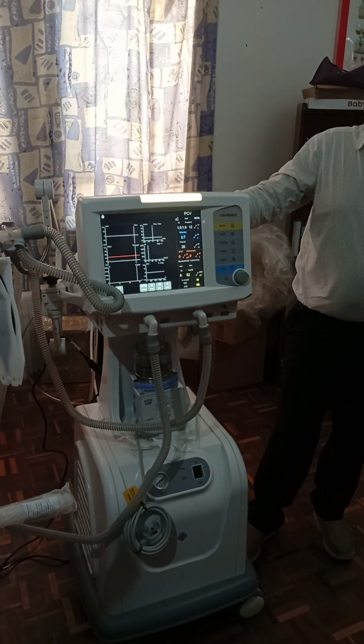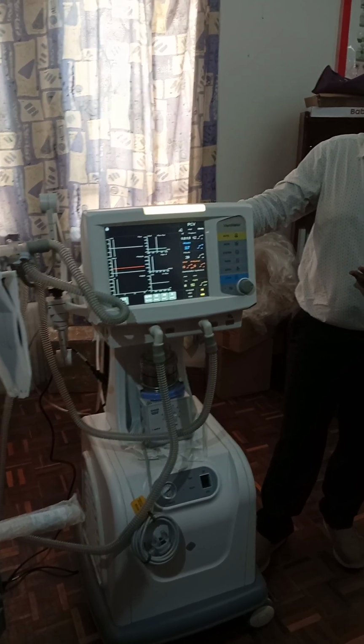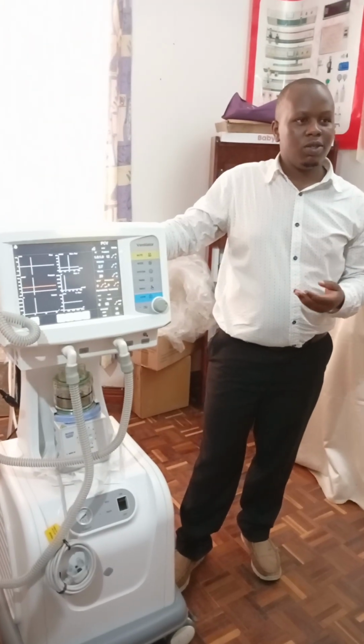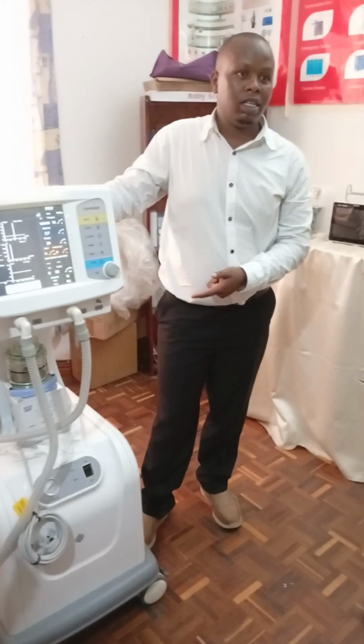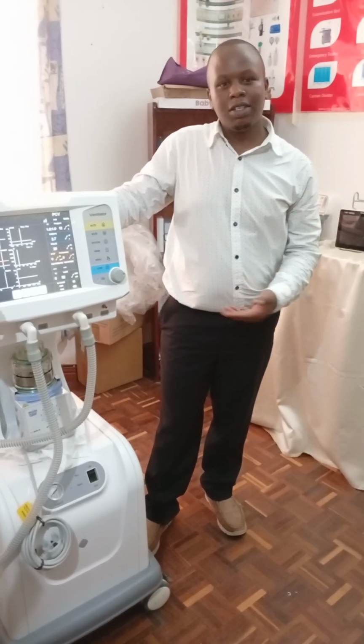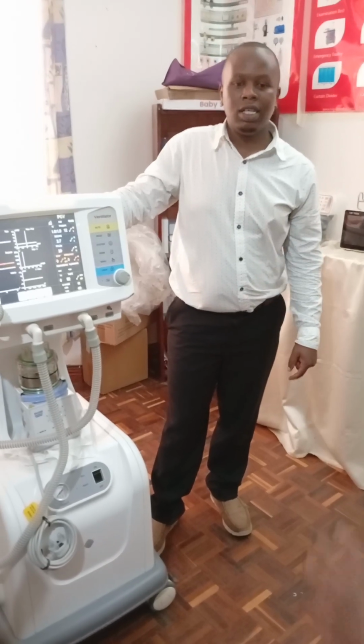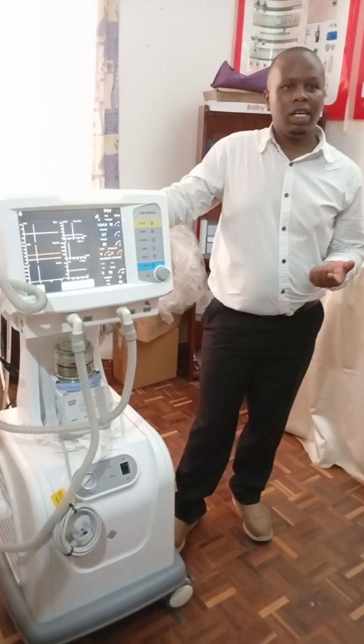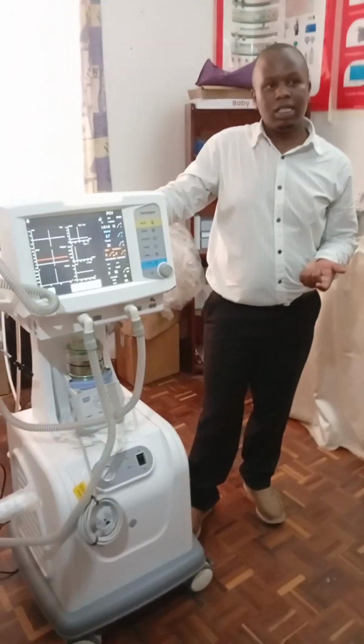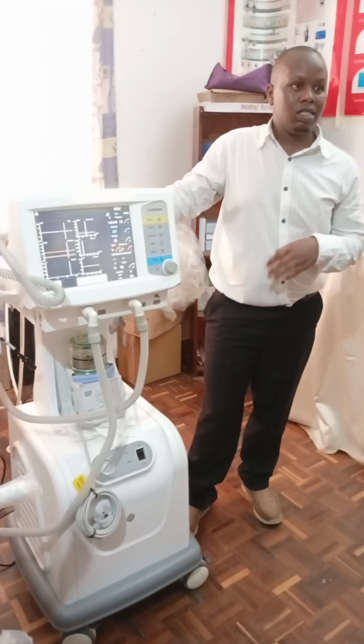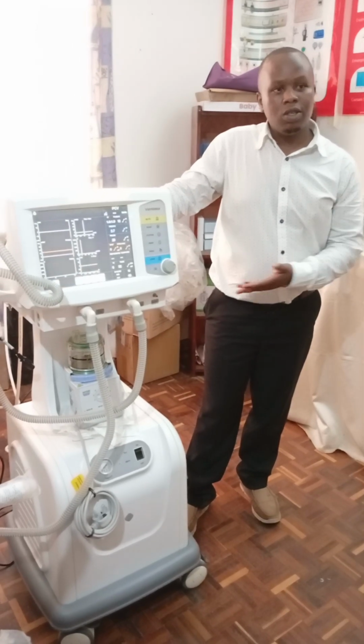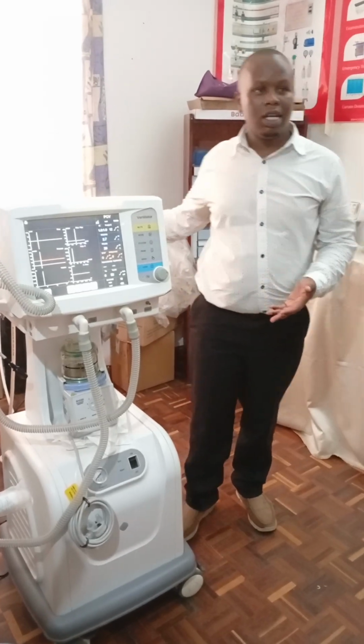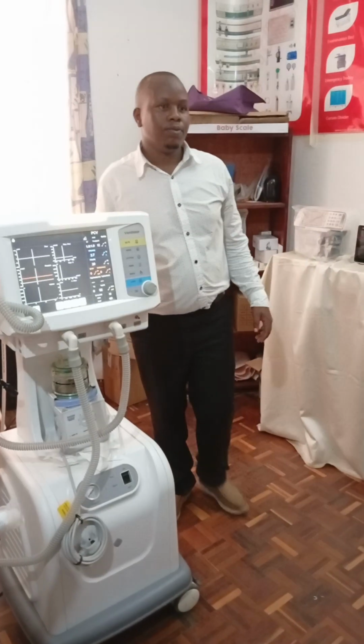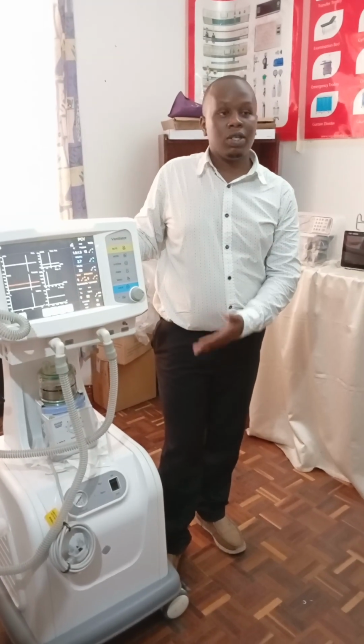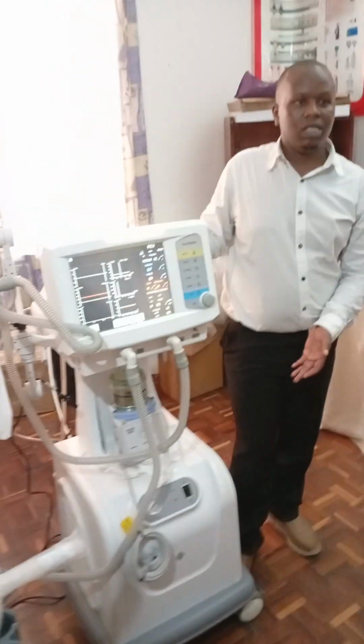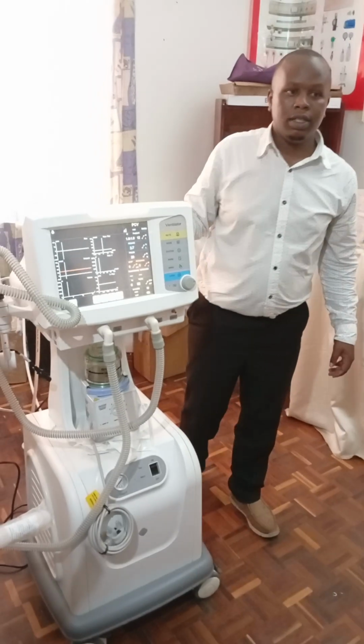For this case, what the company has done is, in a situation where you don't have the medical air, this one comes in handy. So you'll need to just bear with the noise, because you need that medical air. In most cases, you only use medical air for a patient who doesn't literally require oxygen, who is already recovered, but just needs some assistive ventilation. So you'll not be using it frequently. You'll be using either the piped gas or the cylinder. This is just as a precaution, in case you run out of the medical air, it will be able to assist you. Okay.